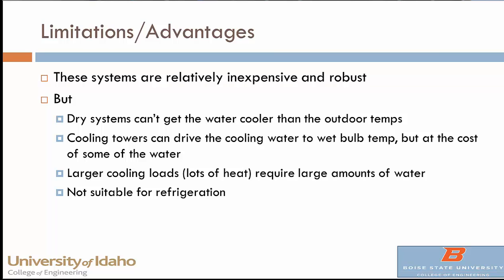If it's a dry system, you can't get the water any cooler than the outdoor temperature — in fact, you need a delta T to reject the heat. So if you're trying to cool below 80 or 90 degrees in warmer weather, you can't do it. With a cooling tower, you use the evaporative power of water, which can drive the temperature down to the wet bulb temperature — as much as 10 or 20 degrees cooler than outside, depending on how humid it is. But you lose water, and with large cooling loads, you're evaporating large amounts of water.